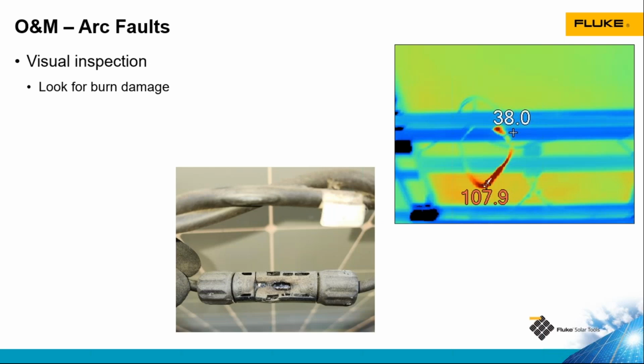Visual inspection can be used to find arc faults. You'll oftentimes find damage that you can see. With this connector here, you can see a little space between the left and right-hand side connectors. I think that this connector was not plugged in all the way, and it started as a series arc fault, a high resistance connection in these two connectors. That melted the plastic off the side of the connector, and then that made a connection to this other wire above it, which then became a parallel arc fault. So you've got a little bit of both parallel and series arc fault going on in that picture.